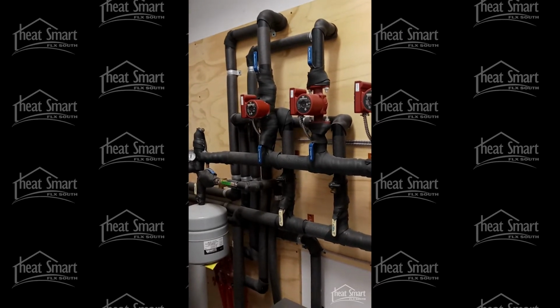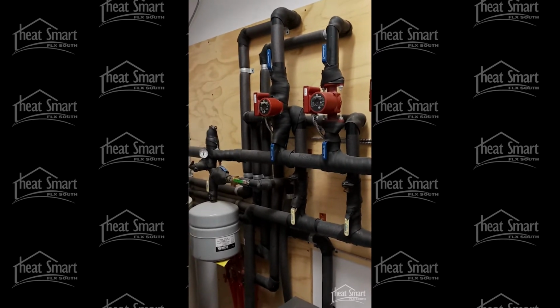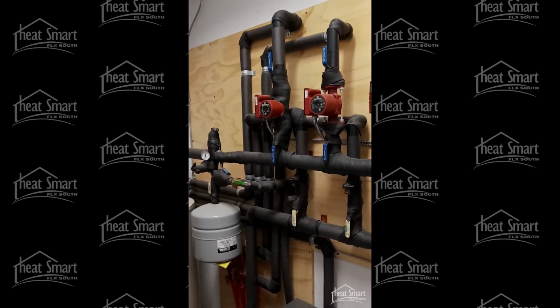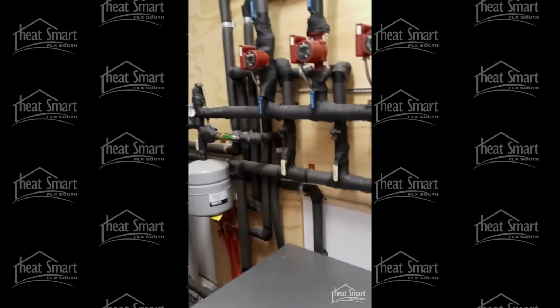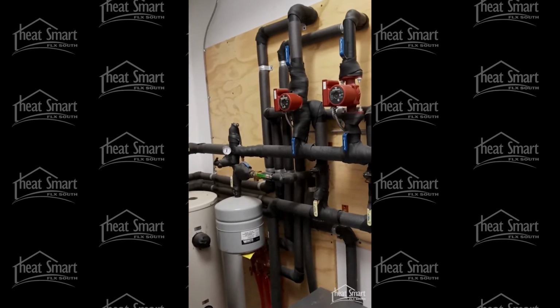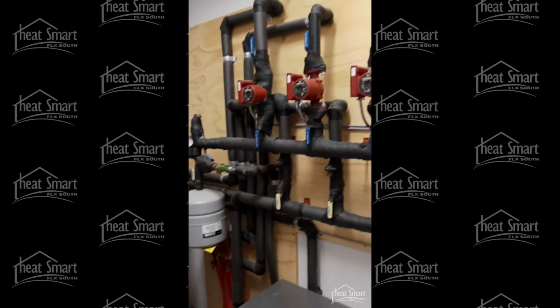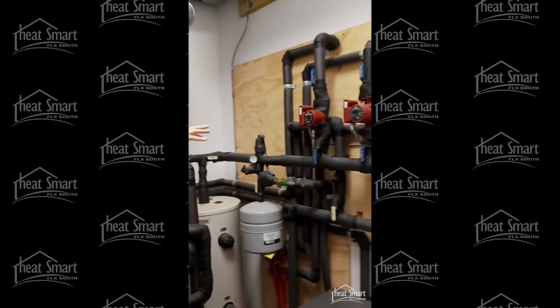When you have heat, you call for heat. One of these two will open, depending on what zone it is, and pump that hot water through the radiant tubing here, or on this side. And for cooling, the heating system isn't heating anything, so those just sit there and don't do anything. But this fan coil kicks on, and you get cold water.